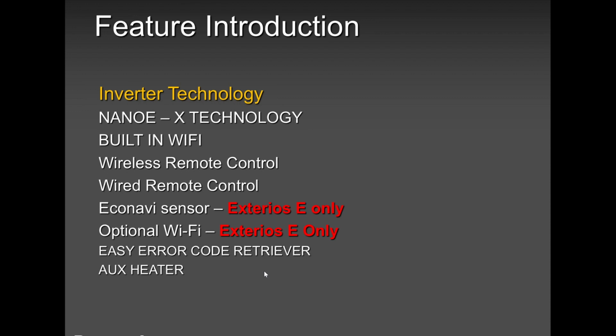Auxiliary heater. What is this about? Auxiliary heater is when the heat pump cannot keep up, especially in very cold areas, up north. Very cold during winter time, it gets into double digits, super cold, and the heat pump cannot keep up. So what happens? If you have this auxiliary heater, you can bring that heater on by using our indoor unit. There is a spot where you plug in and you hook up your auxiliary heater. It could be a hot water coil, it could be a baseboard heater, a boiler, you name it, anything.